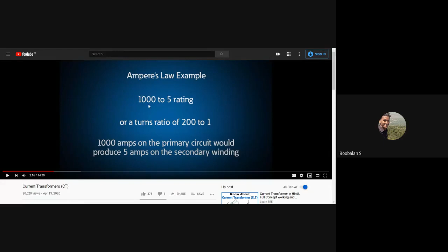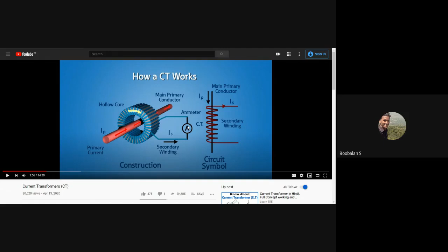If you're measuring 5 ampere over here, then definitely in the conductor 1,000 ampere is flowing. For example, if I'm getting 1 ampere over here, then 200 ampere is flowing here. This is one more small calculation. This is called the turns ratio, a 200 to 1 ratio. So if I get 1 ampere, it means 200 ampere is flowing in that conductor. If I get 5 ampere, it means actually 1,000 ampere is flowing in that conductor.